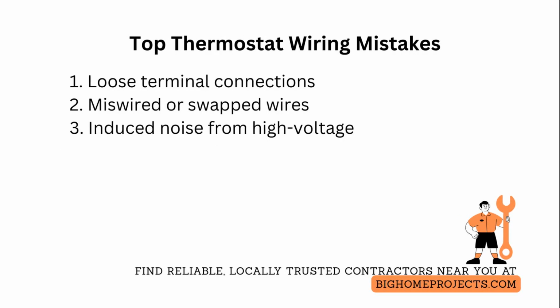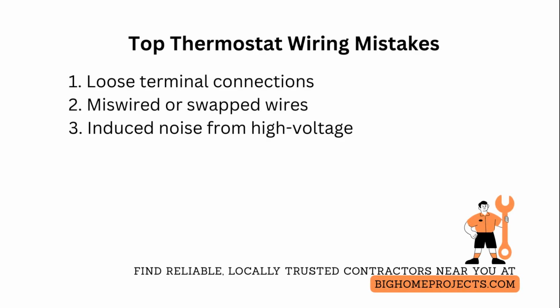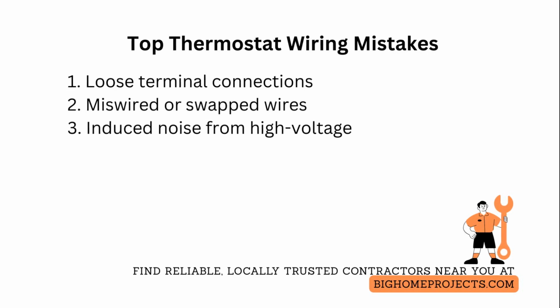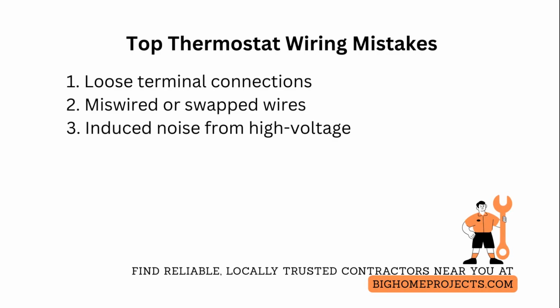One of the top 3 common thermostat wiring mistakes is loose terminal connections, causing intermittent HVAC performance. Fix by cutting and re-stripping, using ferrules on stranded wire, and tightening to manufacturer torque specs.